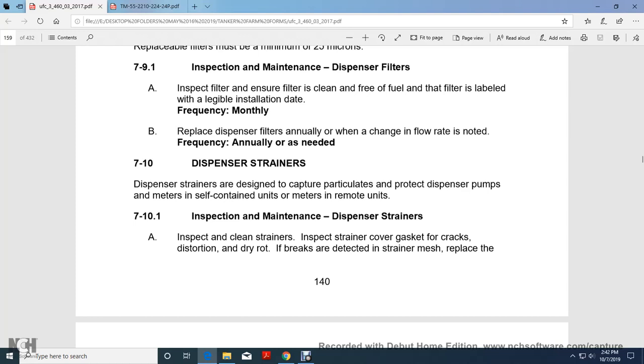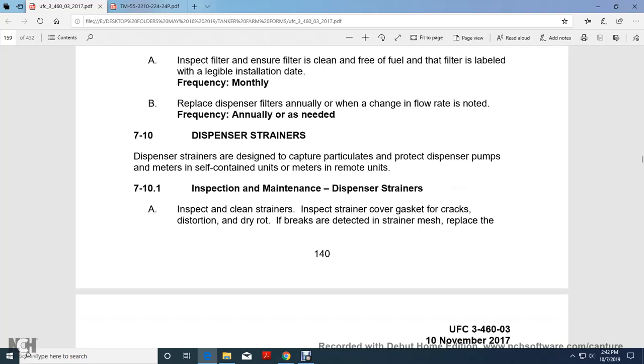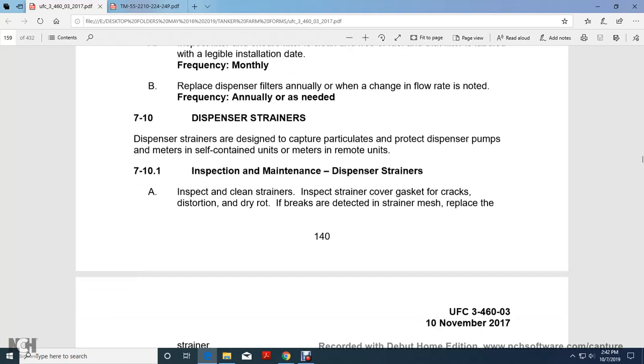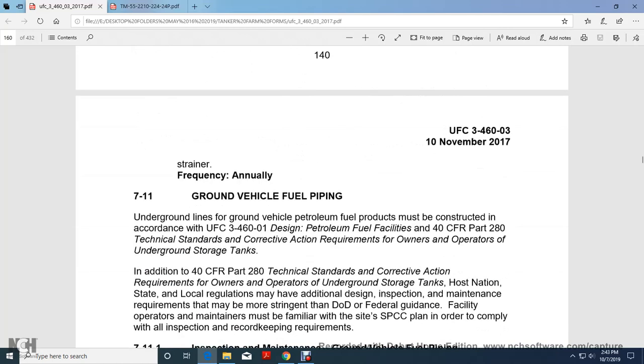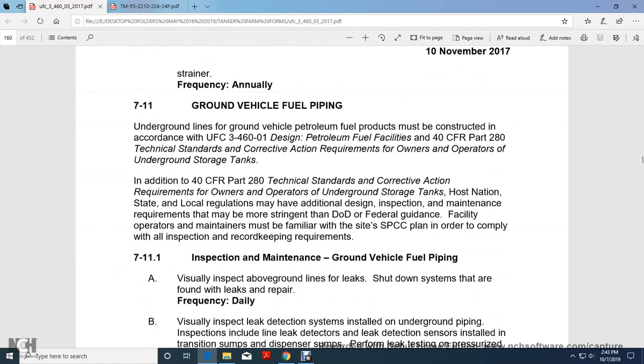Dispenser strainers are designed to capture particles and protect dispenser pumps and meters, in self-contained units, meters and remote units. Inspection and maintenance of the dispenser strainers: inspect and clean strainers. Inspect the strainer cover gaskets for cracks, distortion, dry rot, and breaks, and inspect the strainer mesh for damage. Replace the strainer annually.